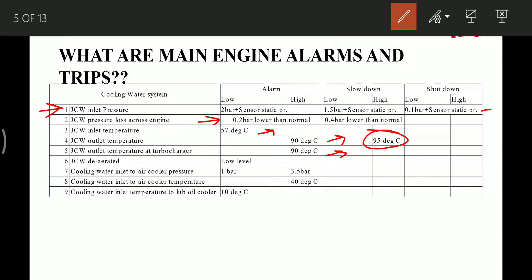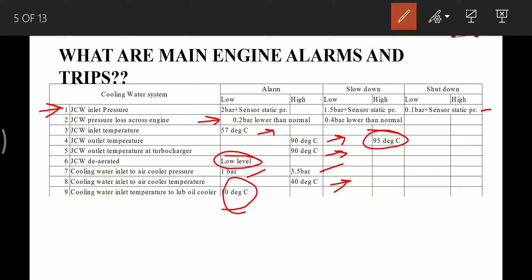Jacket cooling water deaerator gives a low level alarm. Cooling water inlet to air cooler pressure: alarm if below 1 bar or above 3.5 bar. Cooling water inlet to air cooler temperature: high alarm at 40°C. Cooling water inlet temperature to lube oil cooler: alarm when value is less than 10°C. All these values are taken from the MAN B&W manual.